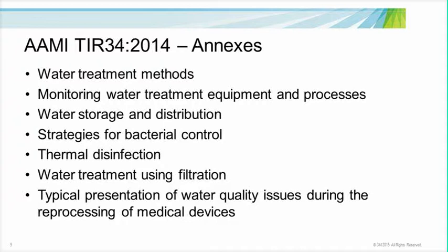Water Storage and Distribution Annex goes into all the information on why and where the water is stored and how it is distributed through the system. The Strategies for Bacterial Control Annex includes sampling, bacterial plating methods, which include spread plating, filtration plating, enumeration, and bacterial endotoxin testing. The Annex on Thermal Disinfection includes the A sub O concept, times, temperatures, and definitions of thermal disinfection.